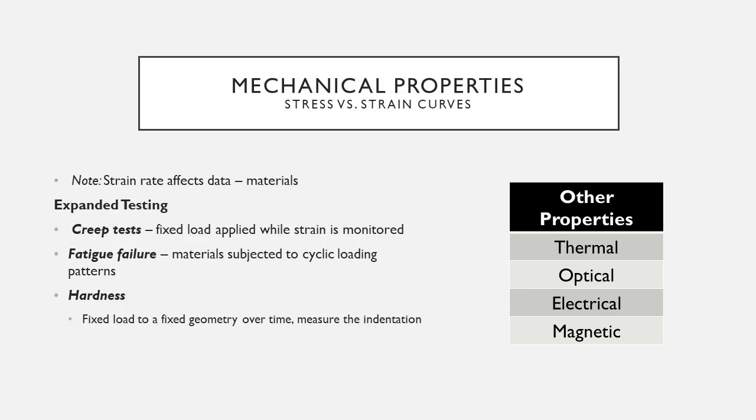Now, you might not go to 100%, meaning you're not going to squish something to an infinitesimally small disk or pull something to twice its height within that minute. You might only go to a 30% strain, but that particular rate is going to be normalized for every sample you take. So if you have a sample that's, say, 10% larger than the other, you're not going to compress or pull them at the same absolute velocity. You're going to make that proportional to the height so that the same strain rate is met between every sample.